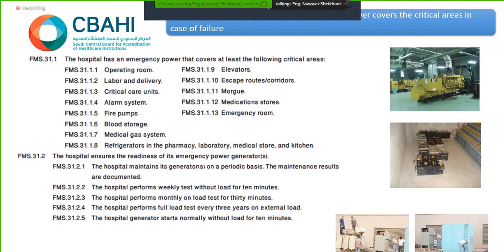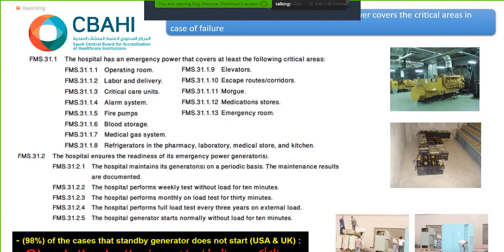The hospital maintains generators, testing generators. Of course, we have three kinds of testing. We have a weekly test with no load, 10 minutes. We have a monthly on-load test for 30 minutes, and we should perform a full load test every 3 years on external load. And of course, once we visit the site, we will ask the electrical engineer to run one of the generators to make sure that it's really running.